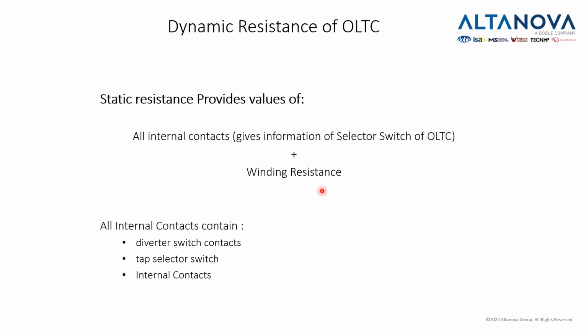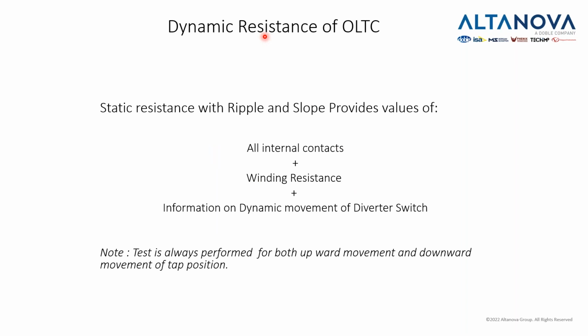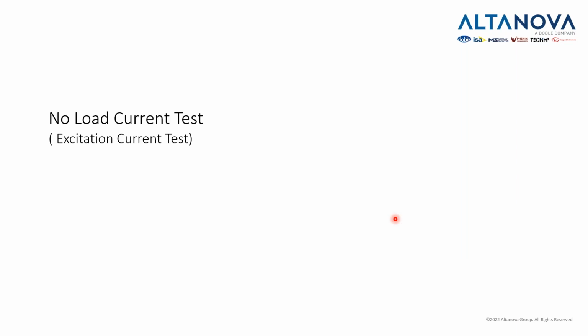If we talk about just static resistance, we measure all internal contacts and the winding resistance. But if we do a dynamic resistance, we also get the information of the movement of the diverter switch. So this is why we do it. This is why it's useful. It is not used in all countries of the world, but in many countries, this is a standardized test.